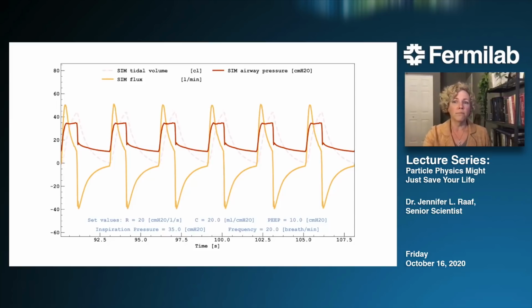For example, the plateau or flat top of the dark red curve is at 35 on the vertical scale, which is what the blue number for inspiration pressure at the bottom tells you was the target value the MVM was told to provide. So the breathing simulator confirms that the MVM provided the right maximum value, and because you see several breath cycles here, it shows there are no crazy outlier pressures occurring at any point during the breathing cycle. It's the same idea if you look at PEEP. The bottom of the red curve gets down to, but doesn't go below, the set value of 10.